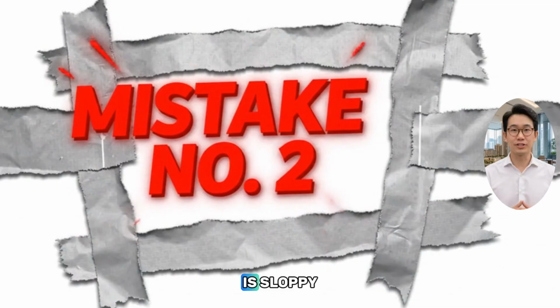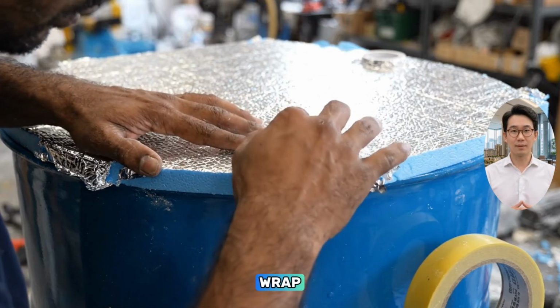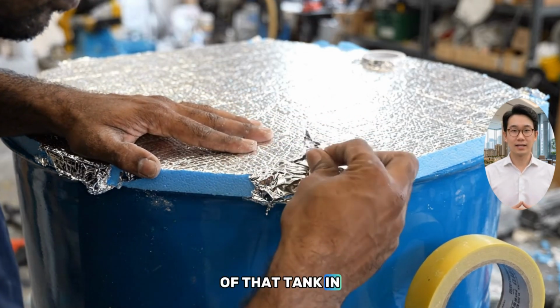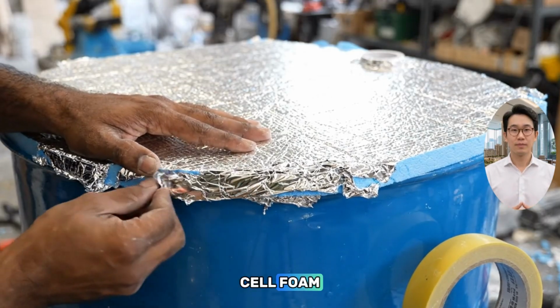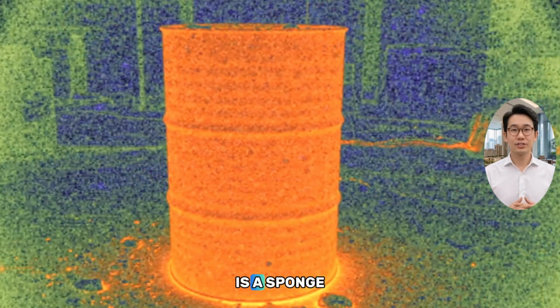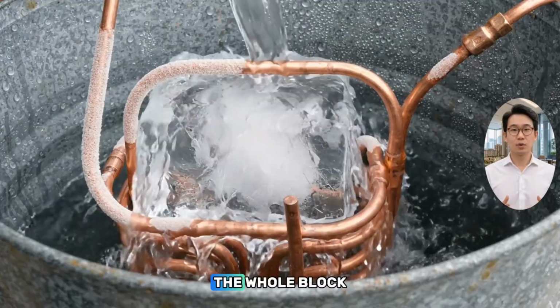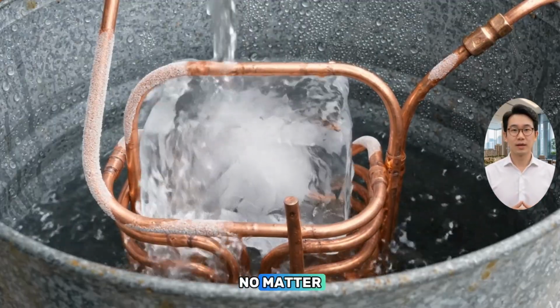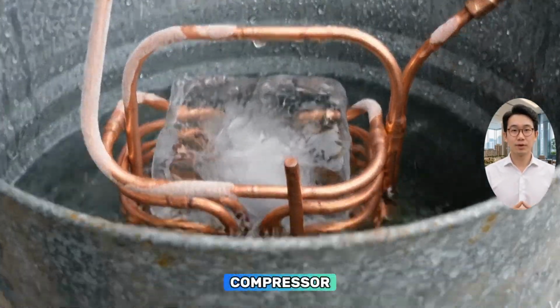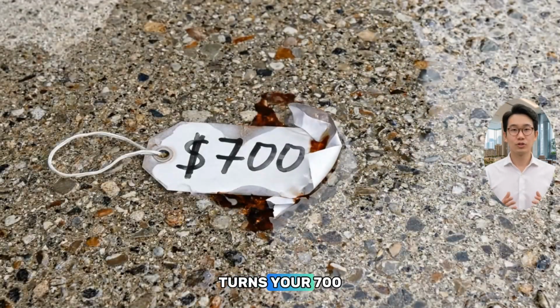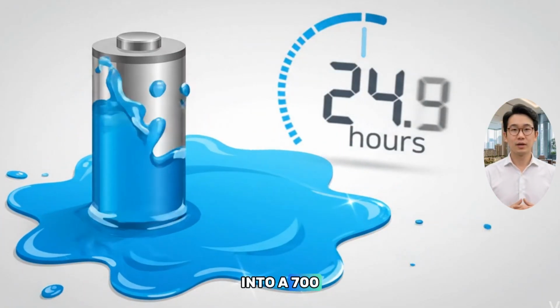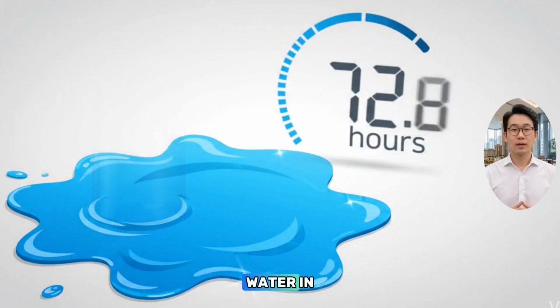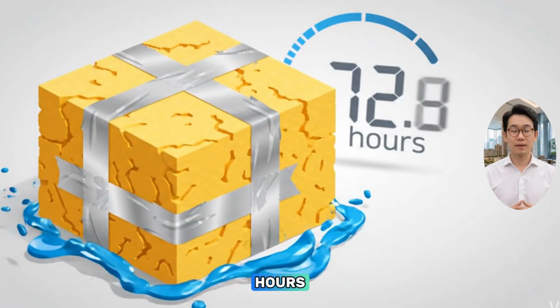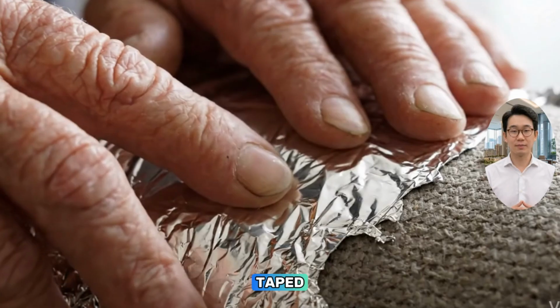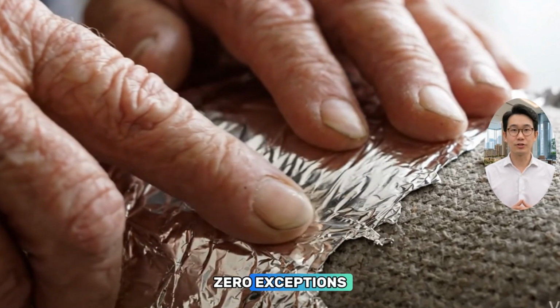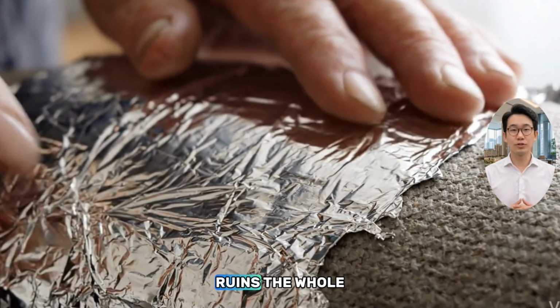Mistake number 2 is sloppy insulation. If you don't wrap every single square inch of that tank in 2 inches of closed-cell foam, including the lid, the ice acts as a sponge for ambient heat. The whole block will thaw in 2 or 3 days, no matter how much solar energy is pumping into the compressor. A poorly sealed barrel turns your $700 thermal battery into a $700 puddle of room temperature water in less than 72 hours. The solution is the foam wrap, taped completely shut, 0 exceptions. One unsealed gap ruins the whole project.